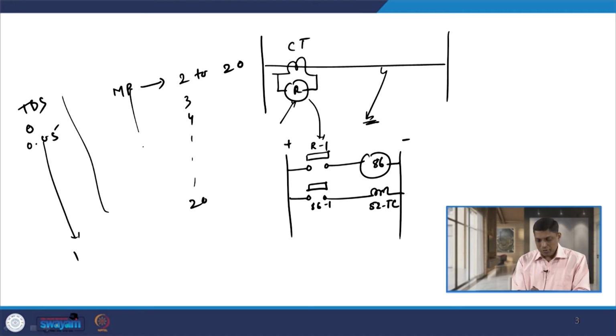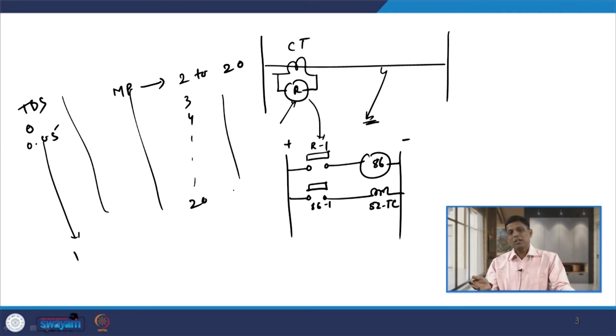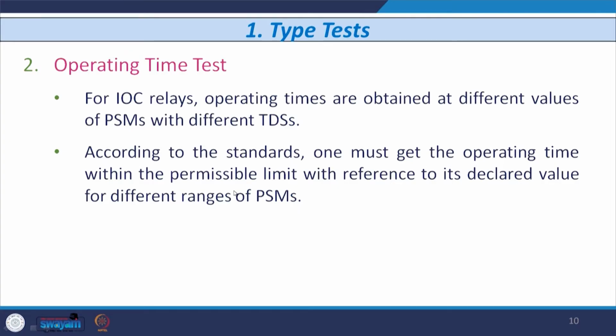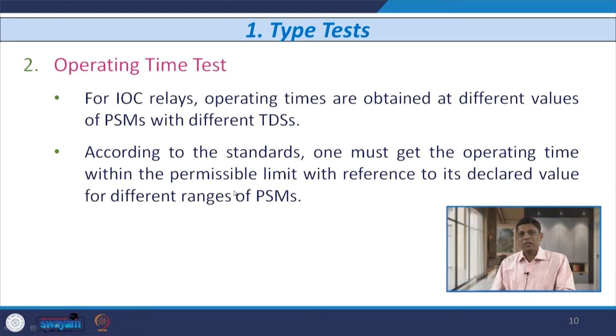For all values of these two, you need to find out the operating time, and then check whether it matches the nameplate, that is, on the nameplate they have given the graph. So, you need to check it with the nameplate value. According to the standard, one must get the operating time within the permissible limit or range with reference to the declared value for different ranges of multiple of pickup current or plug setting multipliers. So, this is a very important point.